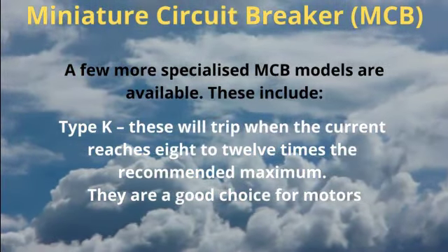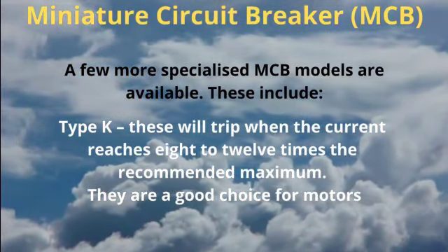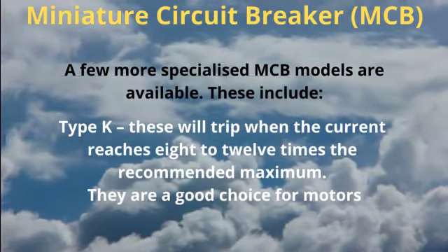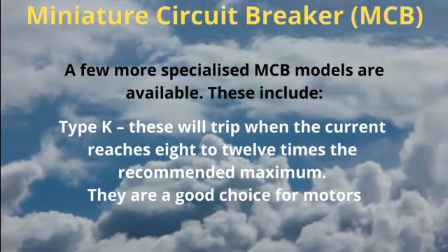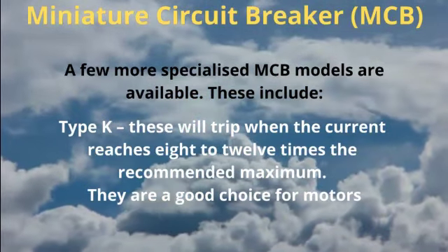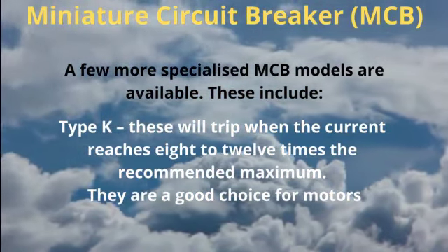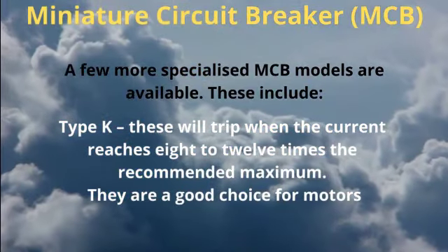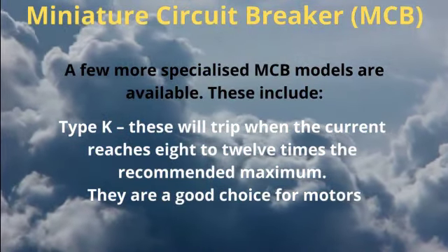A few more specialized MCB models are available. These include Type K and Type Z. Type K MCBs will trip when the current reaches 8 to 12 times the recommended maximum. They are a good choice for motors.